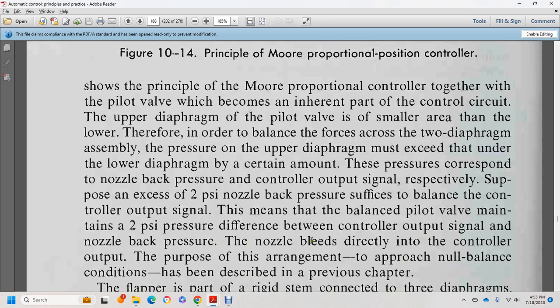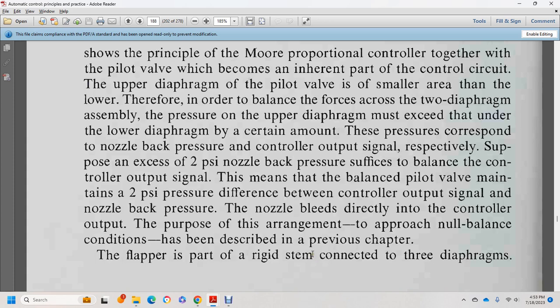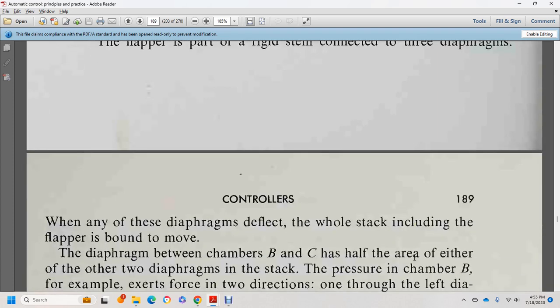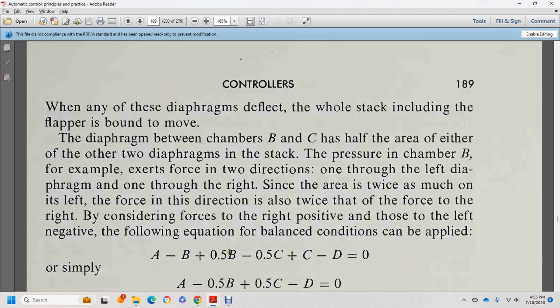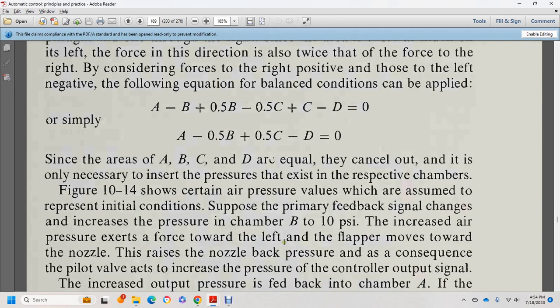Assume 2 psi nozzle back pressure is needed to balance the controller output signal. The balance pilot valve maintains the 2 psi pressure difference between the controller output signal and the nozzle back pressure. The nozzle connects directly to the controller output. The stack consists of diaphragms connected by a stem. Any diaphragm deflects the entire stack, including the flapper. Movement of the diaphragm between chambers B and C has half the effect of either of the other two diaphragms. The balance equation is: A − B + 0.5B − 0.5C + C − D = 0, simplifying to A − 0.5B + 0.5C − D = 0, where areas A, B, C, D cancel out.